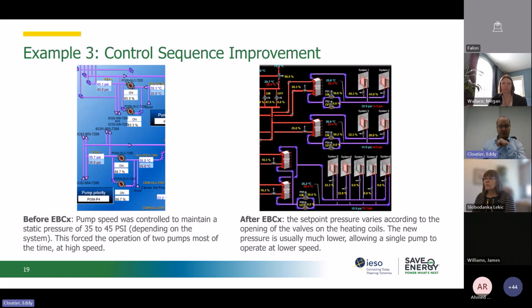We completely modified the sequence so that the speed of the pump was determined according to the opening of the different heating valves of the system, and that's what we see on the right, which made it possible to considerably reduce the required pressure and also, of course, the speed of the pumps to meet that set point pressure. Significant electrical savings were generated in that case also. So these are three examples. I'll give back the presentation to Megan.